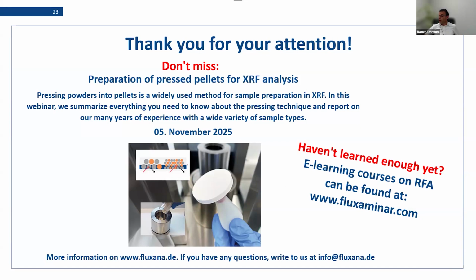There is one question. Those drift samples can be used for method development, for trace element and rare earth element quantification. Yes, you have seen from the table that we cover nearly all elements. And if there is one missing, you can always use the trick that you just measure an element group under the same measurement conditions. And then, of course, you can use also a neighbor element, which is available in the drift correction sample, to do also drift correction for elements which are not present.